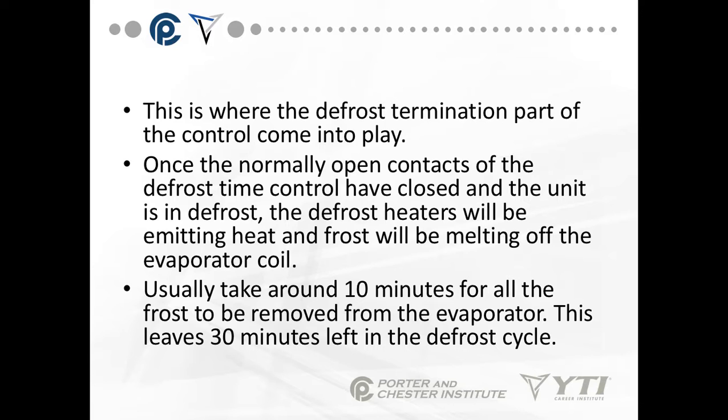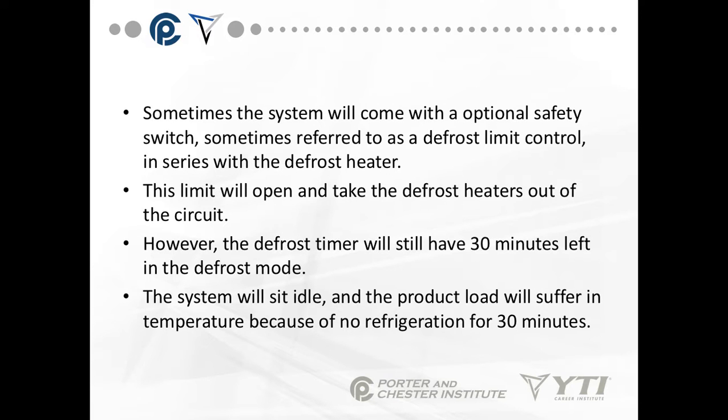Once the normally open contacts of the defrost time control have been closed, the unit is in defrost. The defrost heaters will emit heat and the frost will be melting off the evaporator coil. Usually it takes about 10 minutes for all of the frost to be removed from the evaporator, leaving still 30 minutes left in the defrost cycle. At this point, we have two options: either find a way to end the cycle, or continue to add heat to the evaporator for an additional 30 minutes.